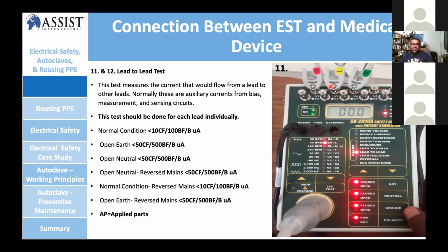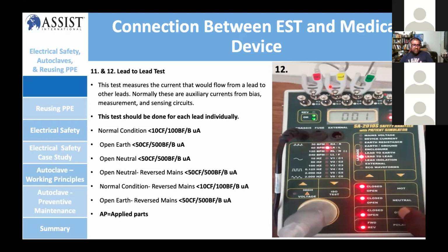It's almost similar to the lead to earth. And on the lead to lead, you can see a reading of 0, a reading of 1, where normally the lead to earth and lead to lead readings will be almost similar. The reason is, if the isolation is good, you're going to get almost similar readings. One is referring to earth, another one is referring to each lead. So the reading will always be similar actually. If lead to earth fails, the chance of lead to lead failing is quite high.